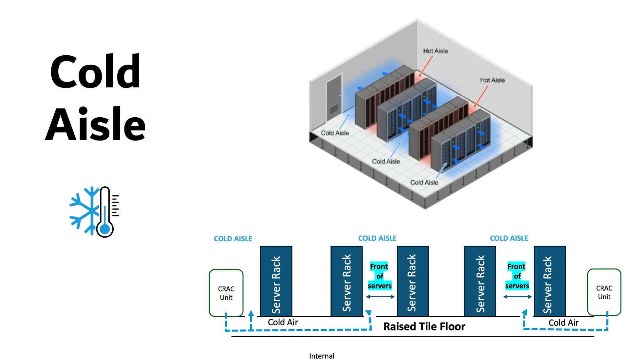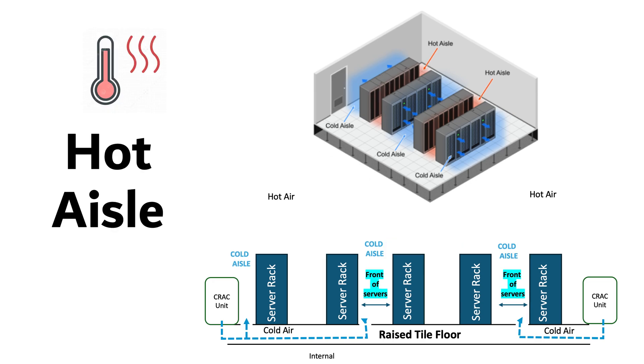The hot aisle is the aisle where the back of the servers, which expel hot air, face each other. Hot air is exhausted into the aisle from the servers and then directed into the air conditioning system for cooling. The goal is to isolate the hot air to prevent it from mixing with the cool air so it can be efficiently removed from the data center.